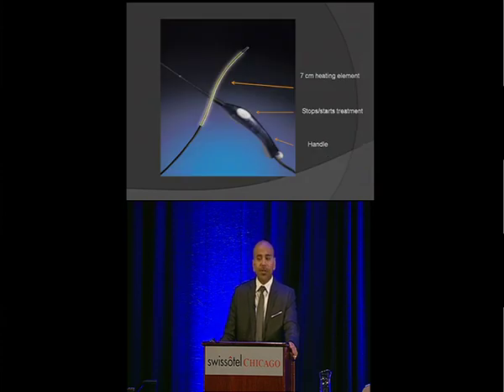This is what the catheter looks like. It has a 7-centimeter heating element, and there's also a shorter 3-centimeter coil that's available for treating shorter segments. You have a handle that has an on-off or a start-stop button, and a port at the end of the catheter to deliver a wire to get through tortuous segments.